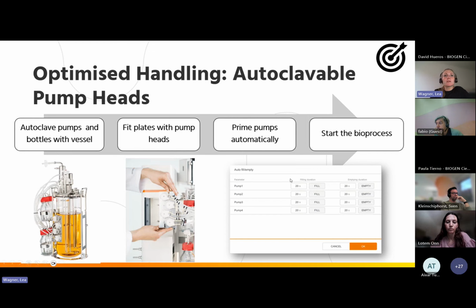Before each process, the customer needs to fill the tubes of the pumps up to the top plate, so that the controller is not confused by pumping in only air. And after the process, the tubes are emptied for autoclaving, and the customer does not have to do this all manually, but can, as you can see here in the screenshot, choose a filling or emptying duration, and then prime the pumps automatically and in parallel, so not one after the other, but maybe fill them for 20 seconds, all pumps in parallel, and then do the fine tuning manually. So this saves money, saves time at the end, and improves the workflow of the customer.